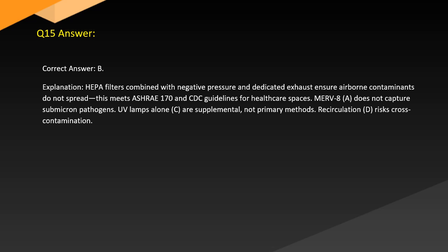Answer. Correct answer: B. Explanation. HEPA filters combined with negative pressure and dedicated exhaust ensure airborne contaminants do not spread. This meets ASHRAE 170 and CDC guidelines for healthcare spaces. MERV 8, A, does not capture submicron pathogens. UV lamps alone, C, are a supplemental, not primary, method. Recirculation, D, risks cross-contamination.